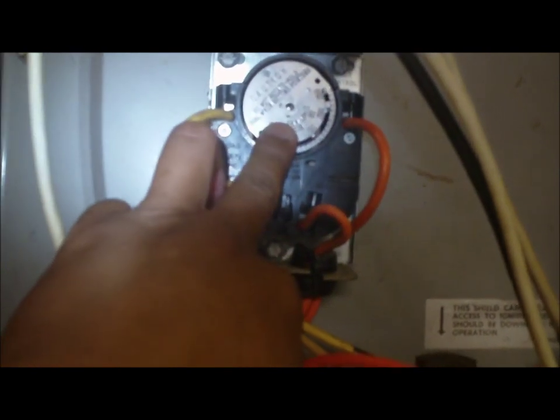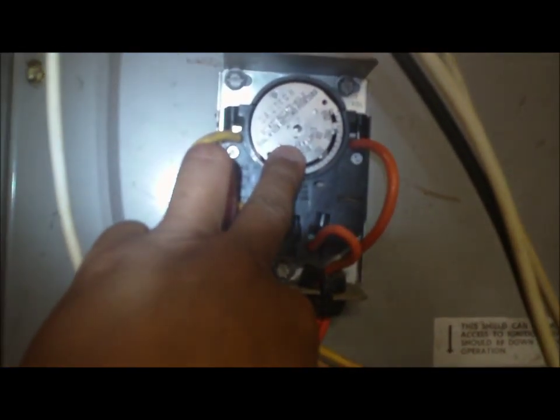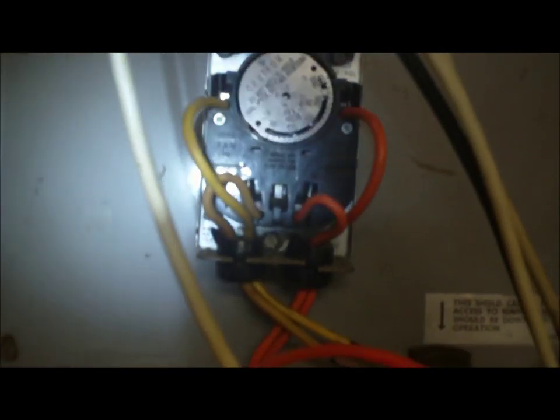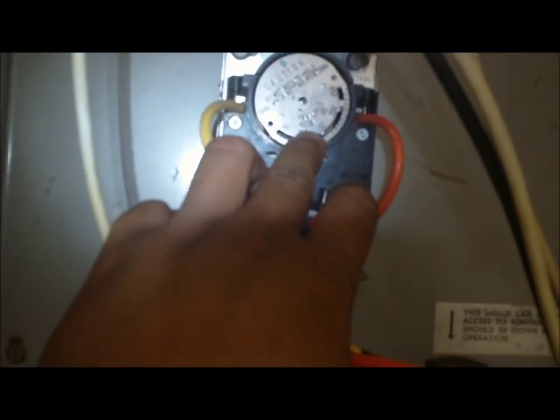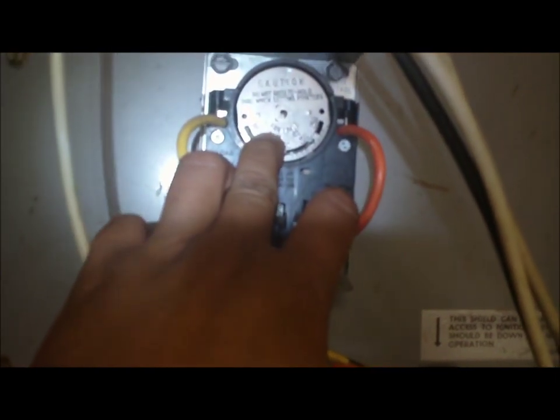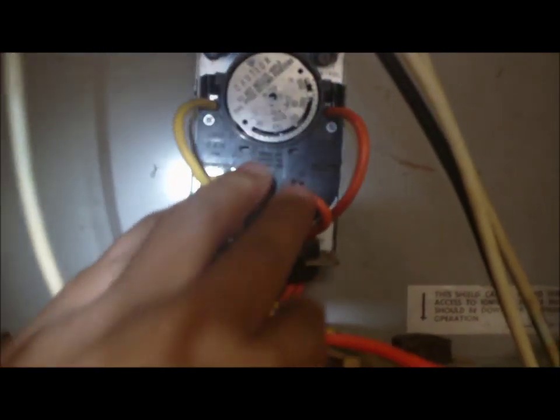Behind this dial right here, there's a bimetal that sticks out to the heat exchanger right behind this panel, and in that bimetal there's a spring. When the spring gets heated, it contracts and turns this dial right here, and in turn, at 150 degrees, it will turn the blower fan motor on low speed.